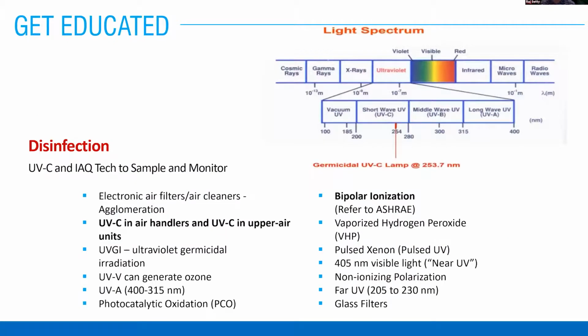Okay, there's a couple other technologies you're going to hear about out there. UVC, ultraviolet radiation, has been used to kill mold on coils for decades. Remember, it needs to be UVC at 253.7 nanometers wavelength. UVV, UVB, UVA all can be used. However, UVV generates ozone, and 253.7 nanometers is the best germicidal wavelength.